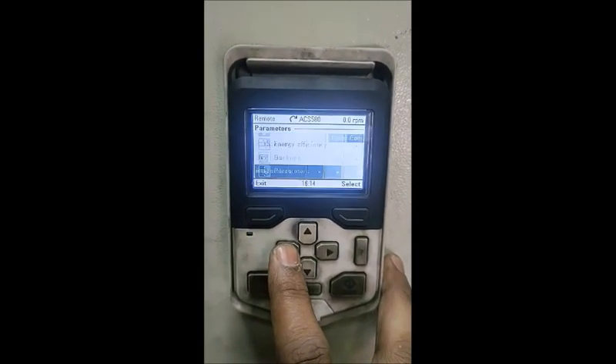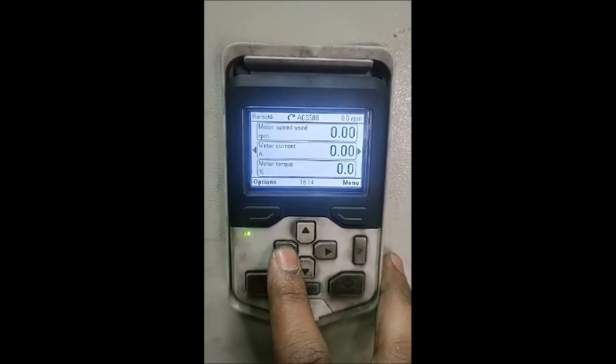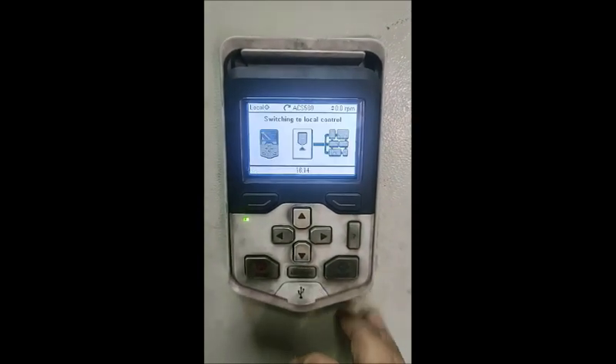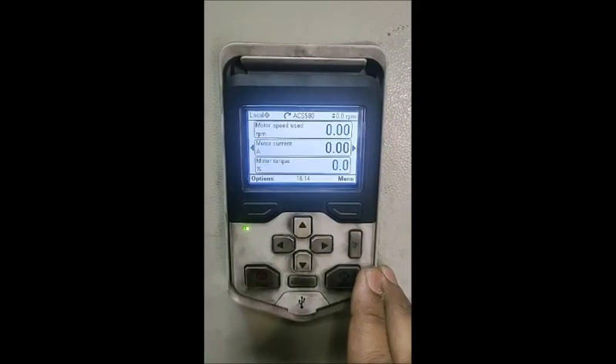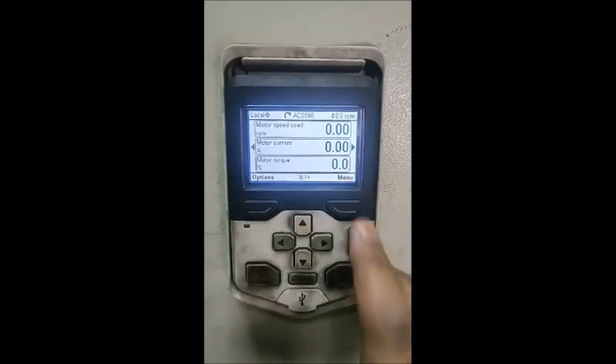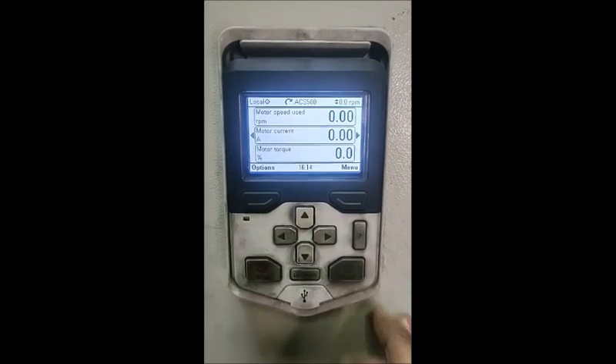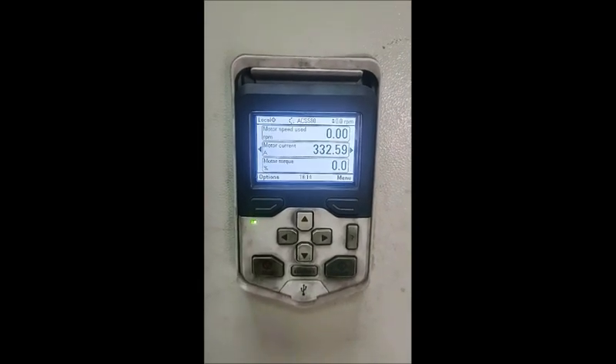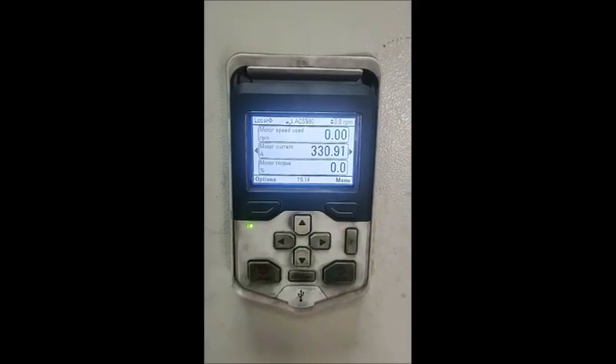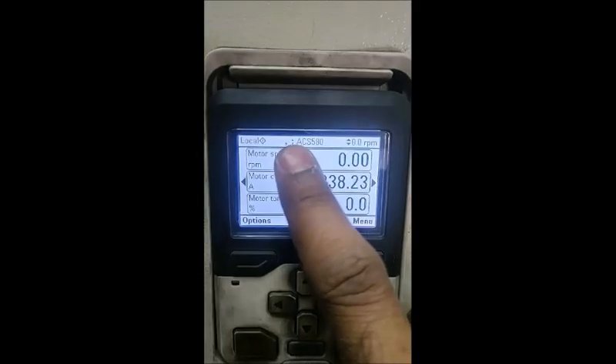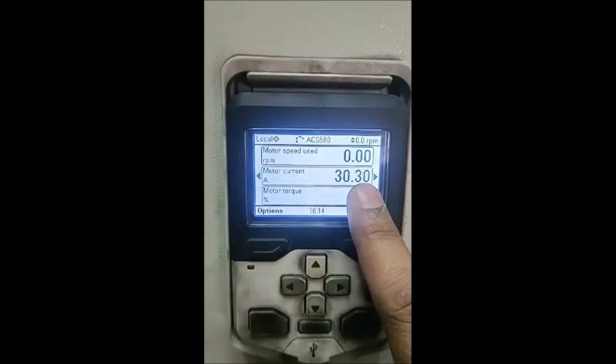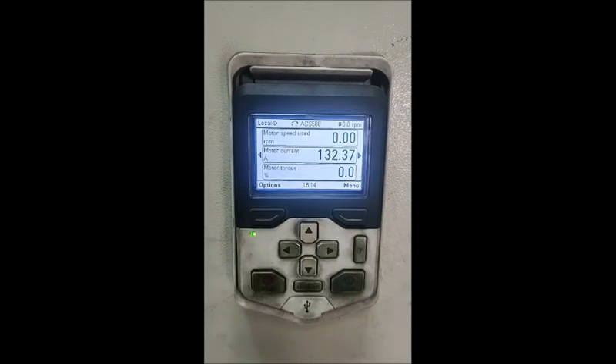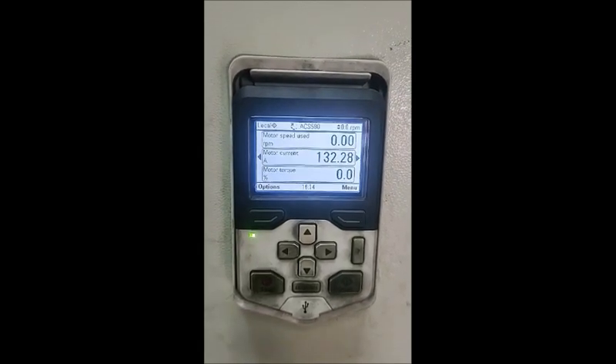We will come back to the main display by pressing the left button. The system is currently in remote condition. We will bring it to local by pressing this button, switching into local control. Once it is in local, all the values are zero. We have to press the start button. Here you can see the change in current, but the speed will remain zero because we selected standstill. If you had selected reduced or normal, there would also be a change in nominal speed, but RPM will remain zero in this case. You can see the variation of current.